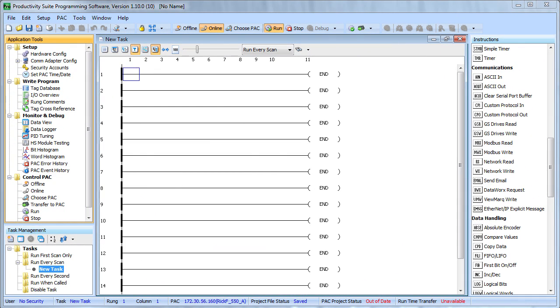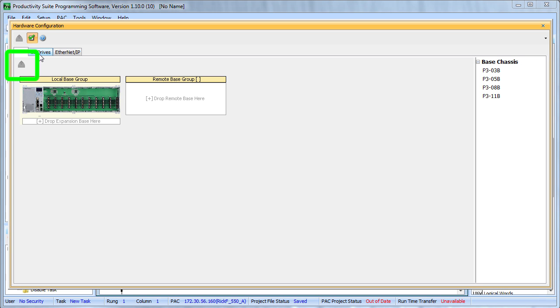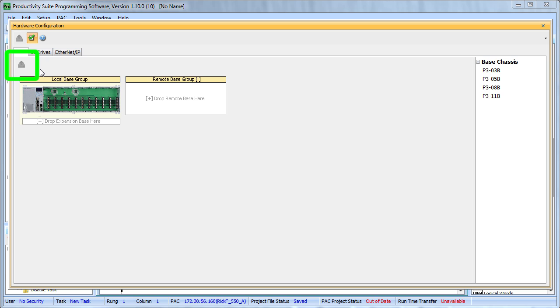And configuring the serial ports is easy. Step 1 – Connect to a Productivity 3000 and go to the Hardware Configuration. Hit the Read Configuration button to auto-discover all the new SCM cards. If this button is dimmed out like this one is, then the controller is in run mode. So we'll flip that switch on the controller to stop mode.